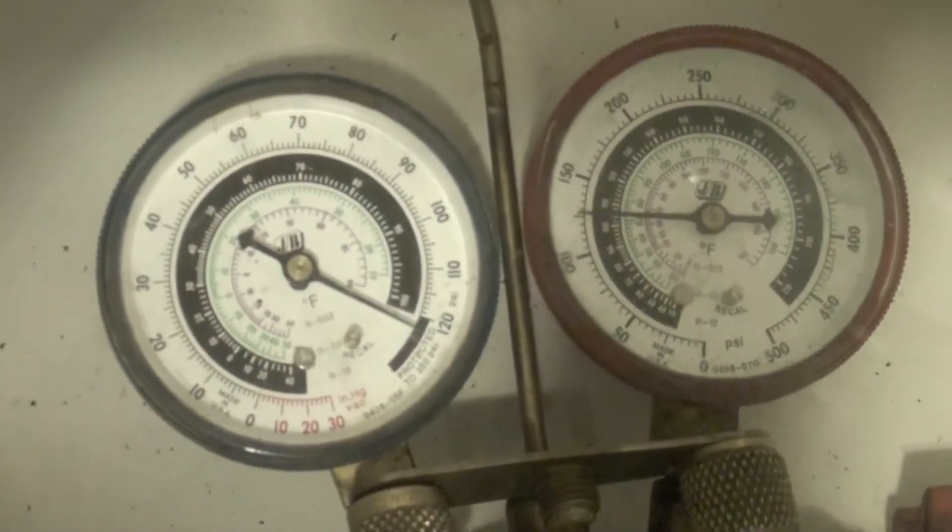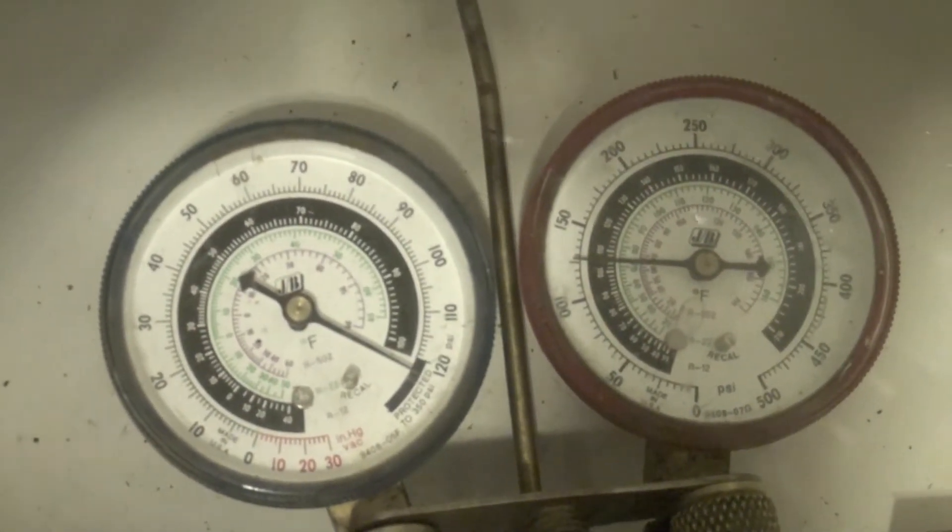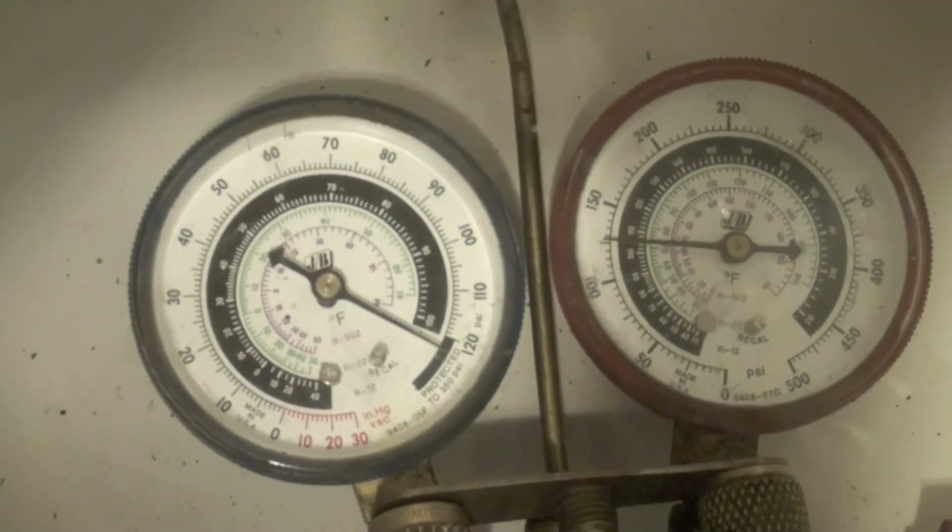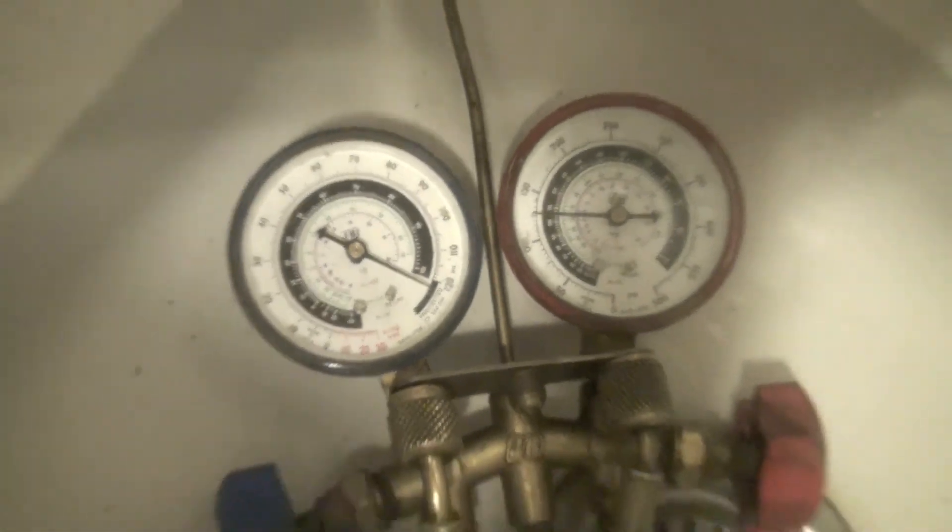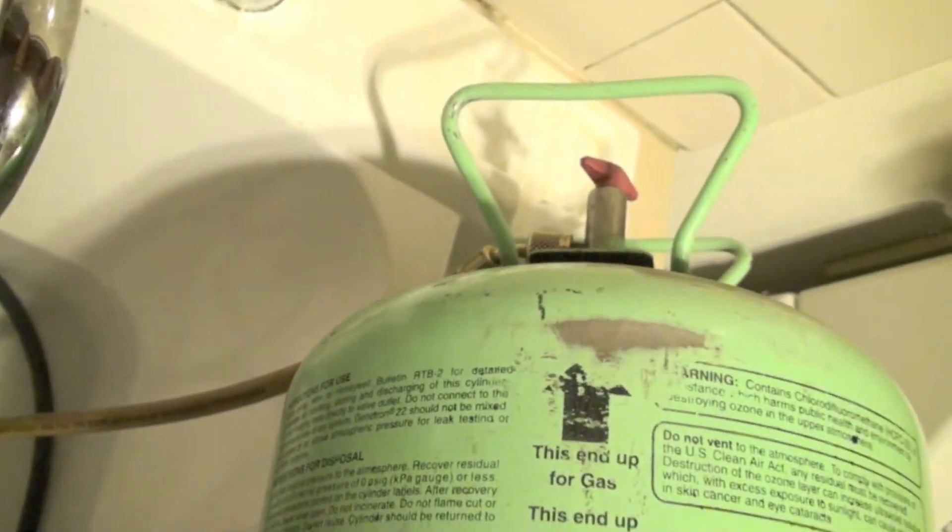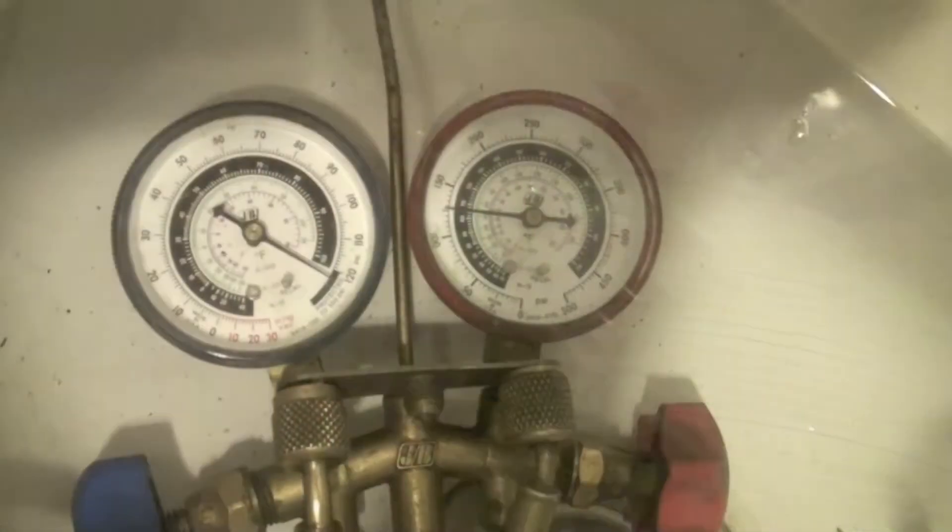Okay, that hose has got a leak. What I've done is, if you look here, the gauge set has pressure in it. That's simply because I have it hooked to a refrigerant cylinder. What we're doing here by putting these hoses in water is finding out if there are any leaks.